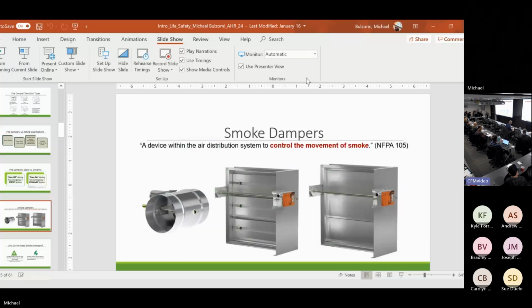Jump into smoke dampers, very simple. There's your NFPA 105 definition. Smoke dampers do one thing: control the movement of smoke. Again, I've got my true round steel V blade. Now I've got an airfoil aluminum smoke damper. I do not have aluminum fire dampers. Anybody care to guess why there's no such thing?